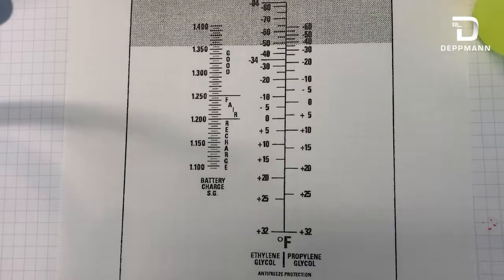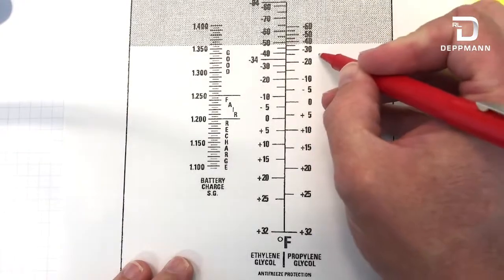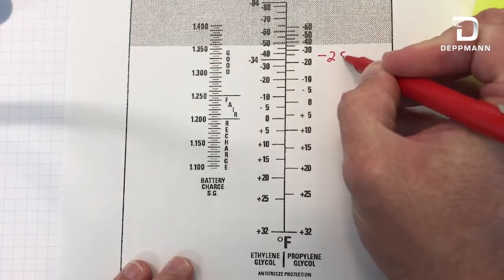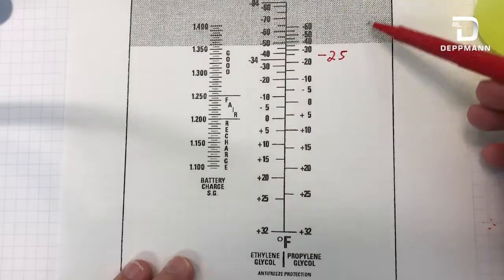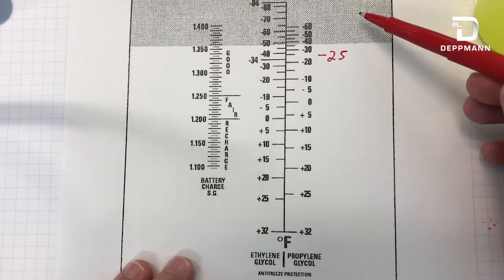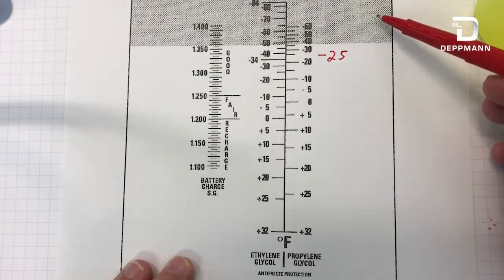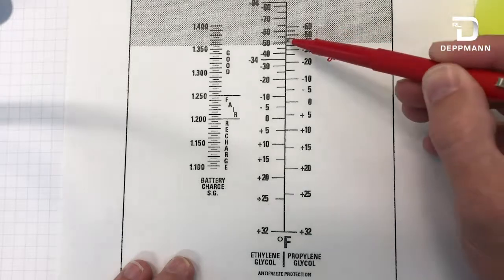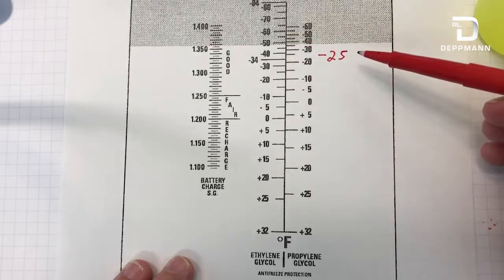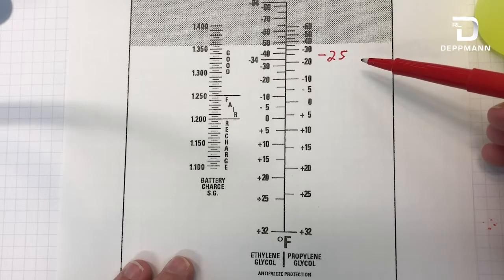I have viewed my sample through the refractometer and I am getting a reading of negative 25. As you can see here in this example, they're showing you the graded area. When you view it through the meter, you will see a noticeable difference in color between the dark and the light. Where that line crosses this scale will be the freeze protection level that you have in your glycol.